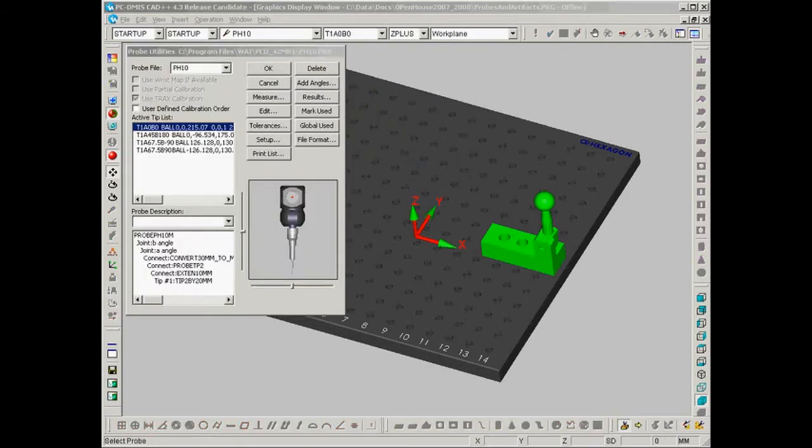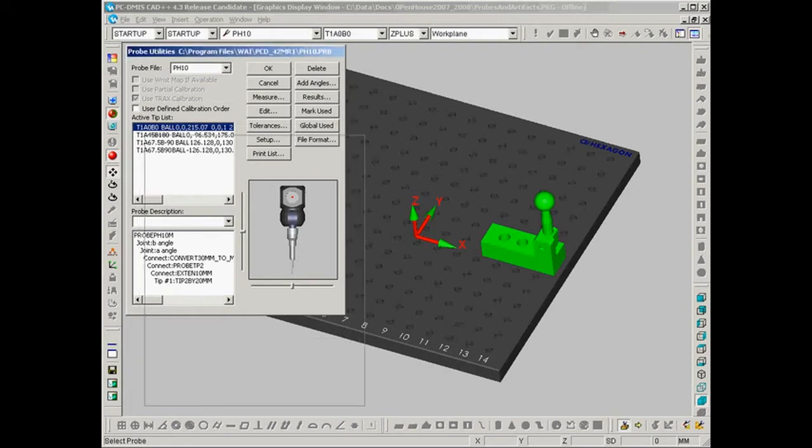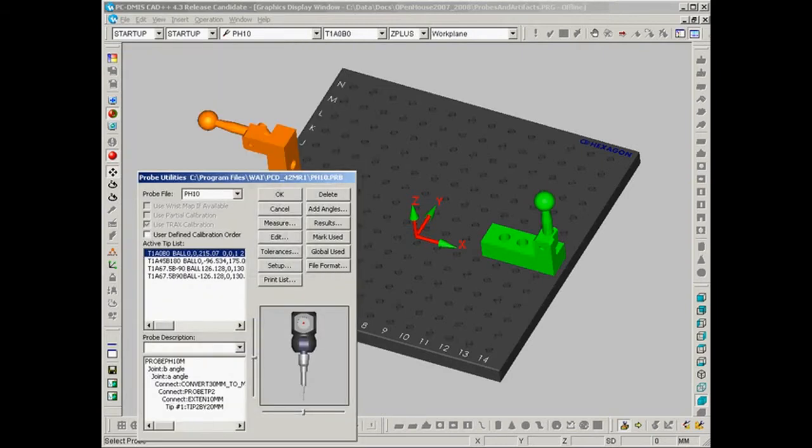The first thing we need to do is to select a probe buildup that will allow access to each of the calibration artifacts without crashing. The probe I have here, PH10, points straight down in the Z minus direction and should afford access to each of these tooling balls.